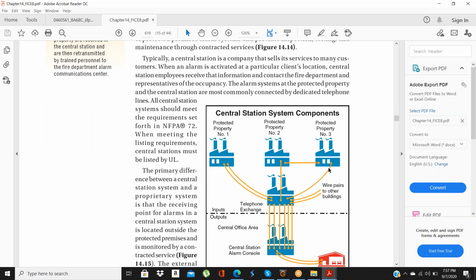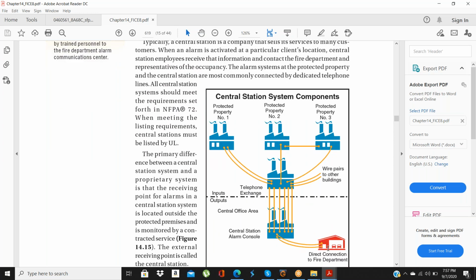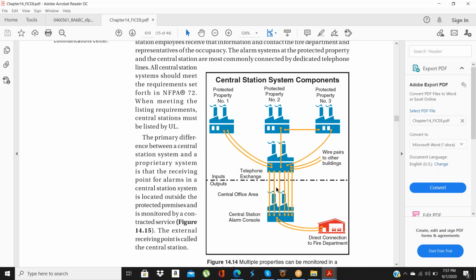In the remote system, the signal comes here and goes directly and automatically to the fire department system, and they get alerted and send their emergency team. Remember, this property should always be outside the protected property zone, because if a fire happens and this property is within that area, it may also get affected by the fire and will not be able to send the signal to the fire department. So this property should always be outside the protected property. Now it's clear?